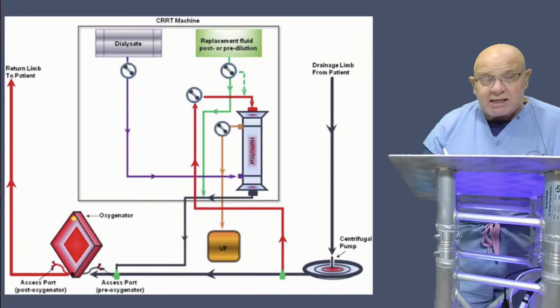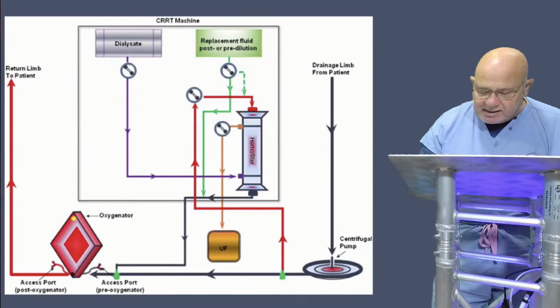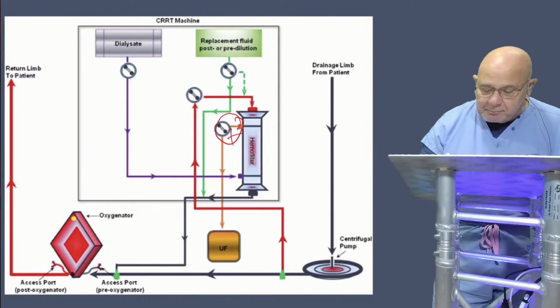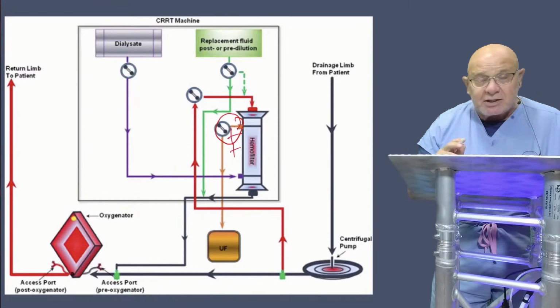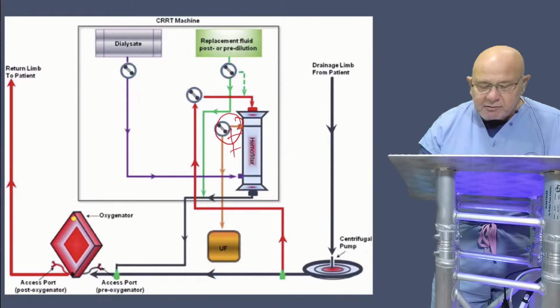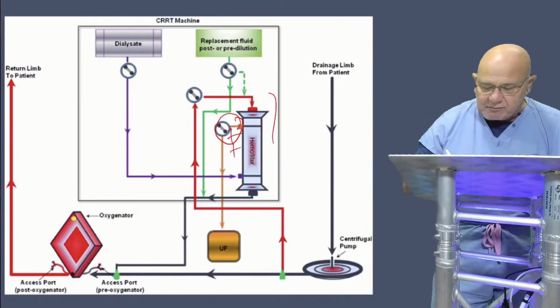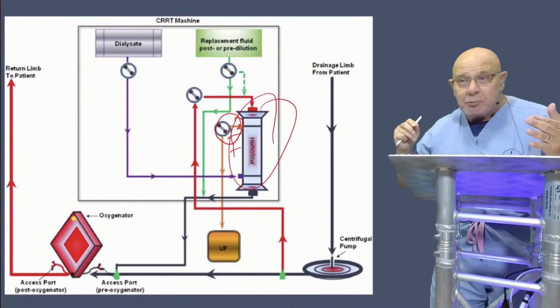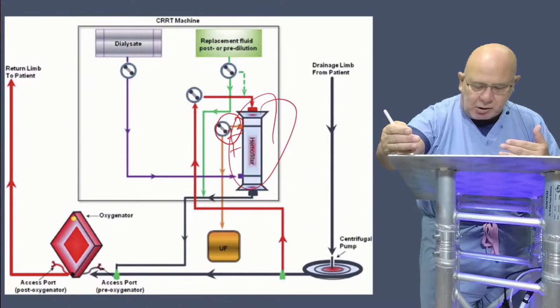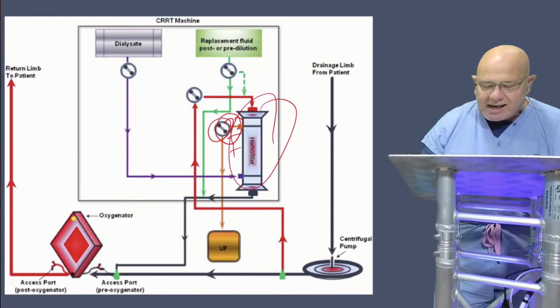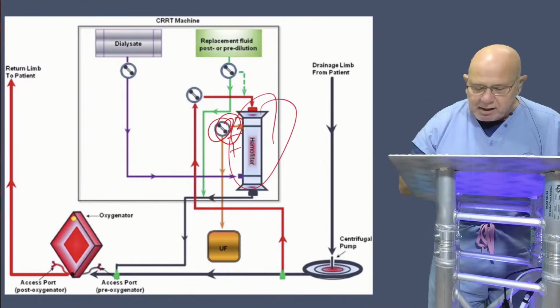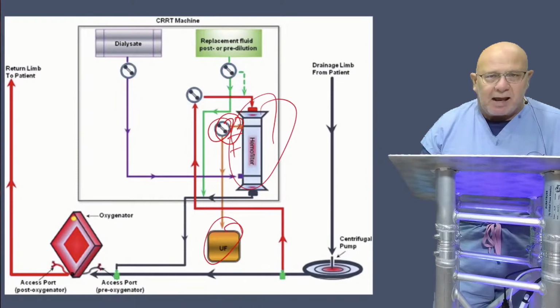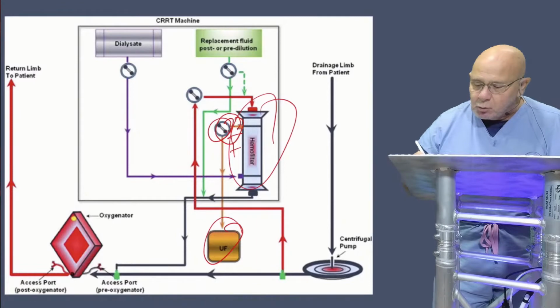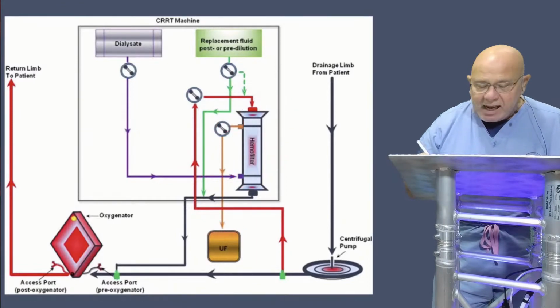In this scenario that you see here, the good thing about it is that this effluent pressure that's before this pump is going to be very, very positive because of how high those pressures are. And you do want that. You don't want this pump, remember what I said, to be pulling the fluid across the hollow fibers in the hemofilter. You want the hemofilter to be pushing the plasma water across the hollow fibers, and for this pump to act more as a dam, controlling the amount of volume that ends up in your effluent bag, your ultrafiltrate waste container. So with that said, I'm going to show you how we do it.